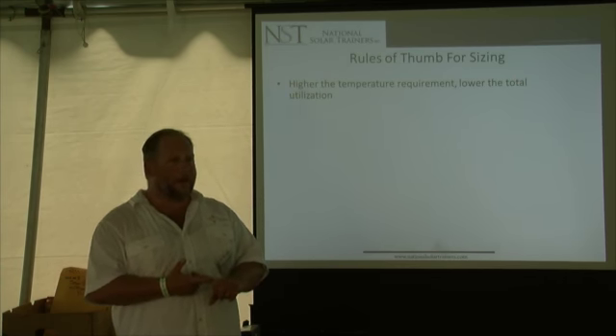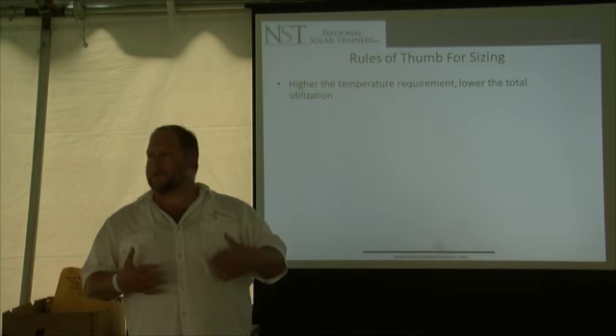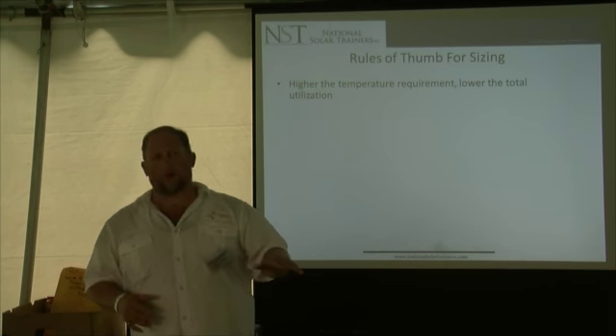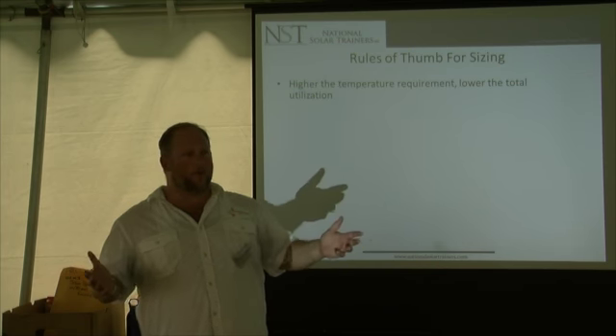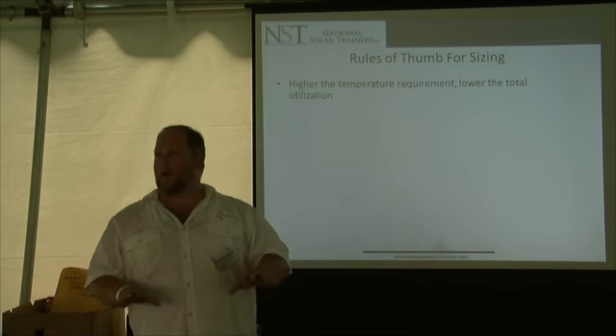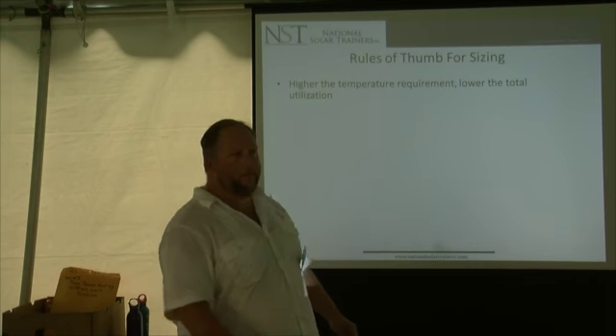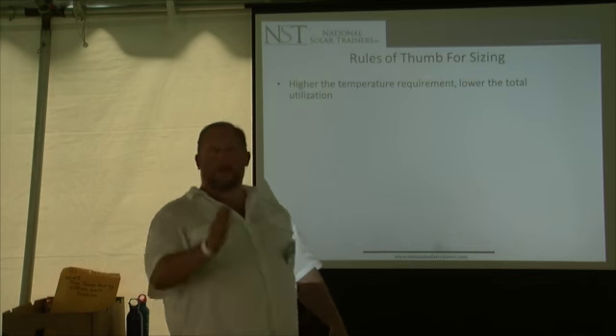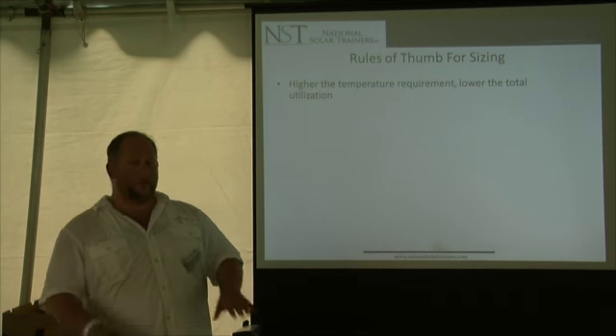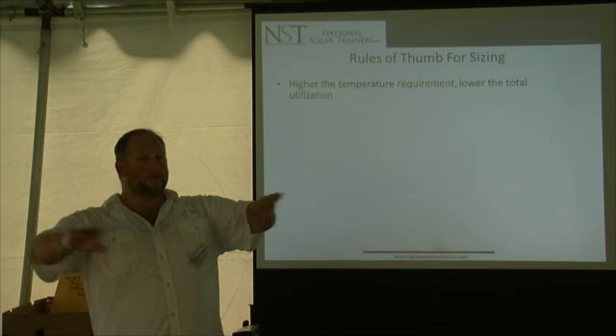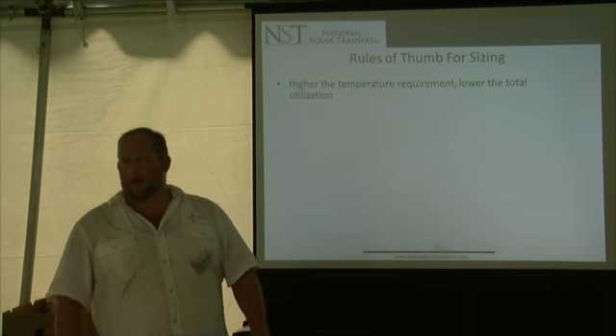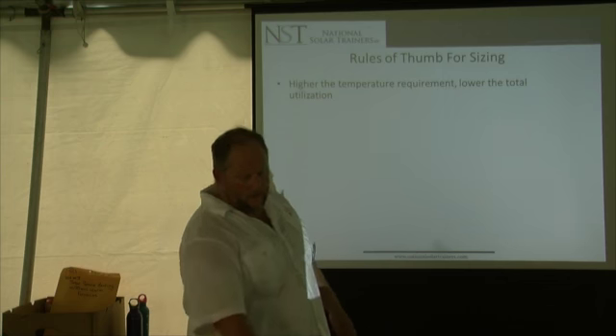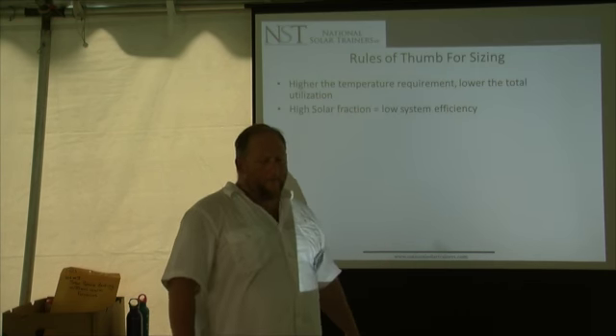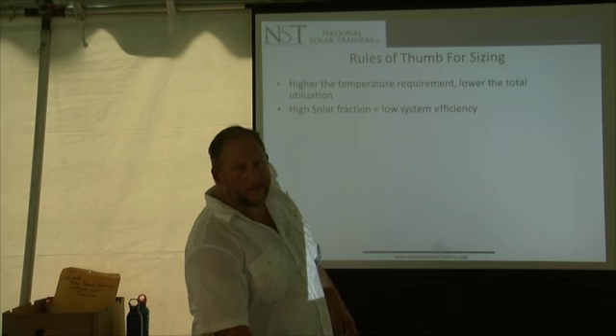In terms of utilizing solar, you've lowered your temperature requirement, which allows you to use more of those available BTUs at a lower quality, a lower temperature. Those have lower temperature radiators now—high efficiency baseboards, double stacked or wall hung ceramic and porcelain, high efficiency low temperature heat dissipators. High solar fraction means low efficiency.